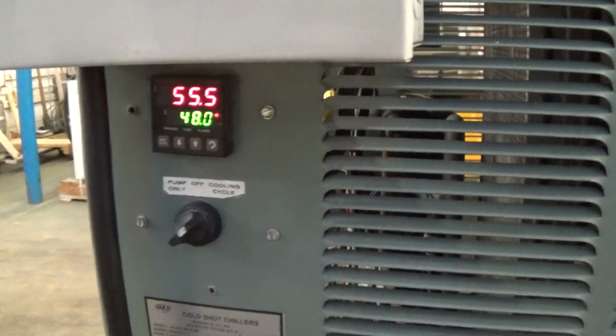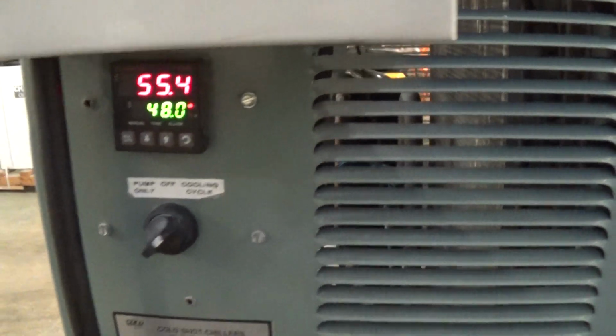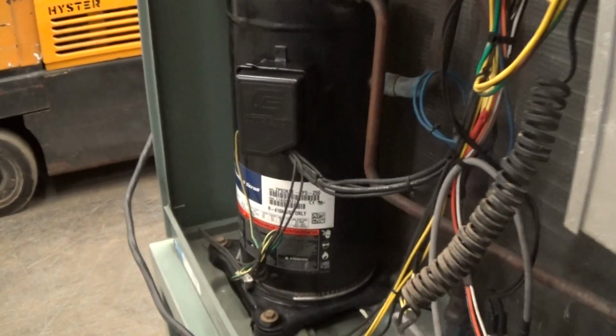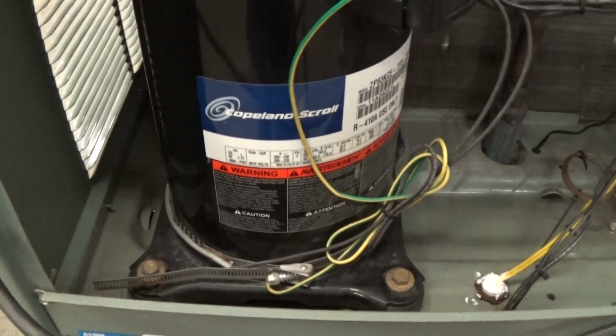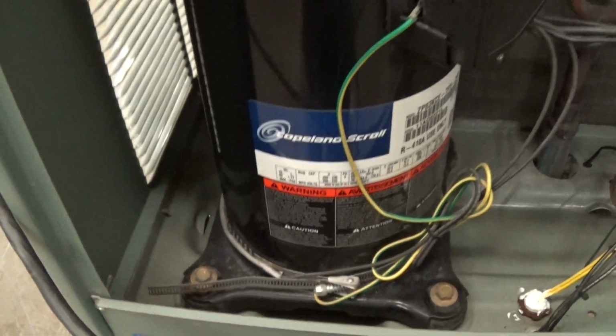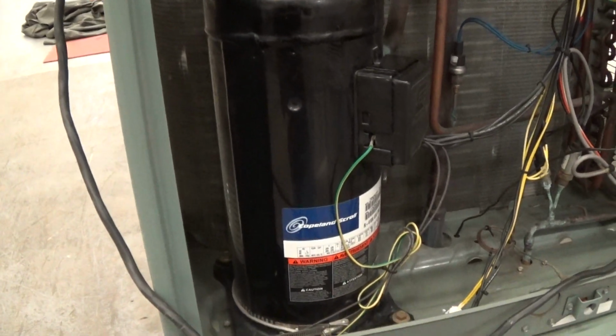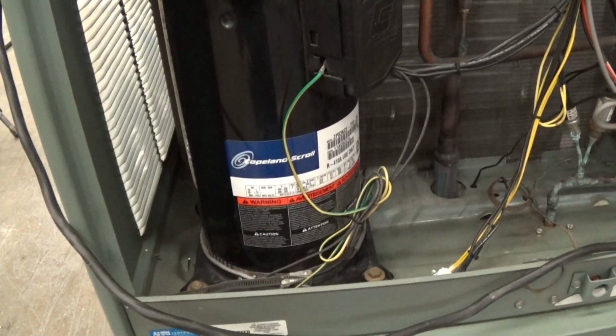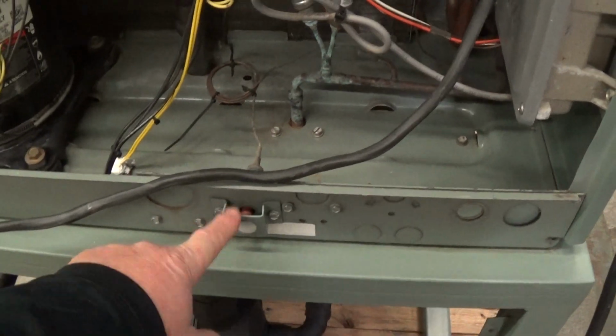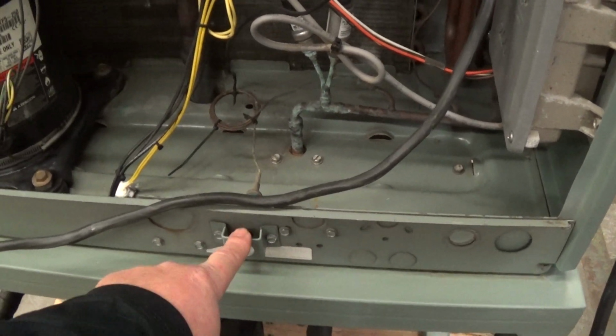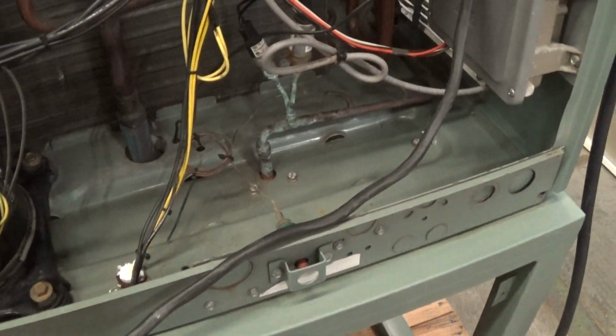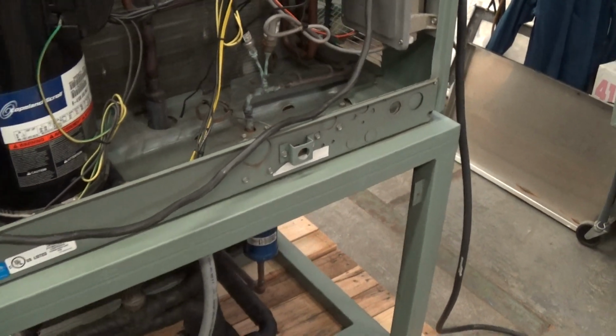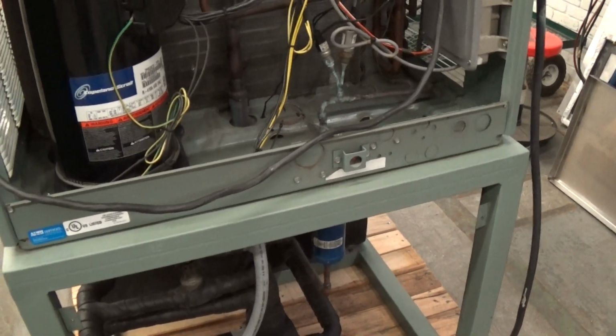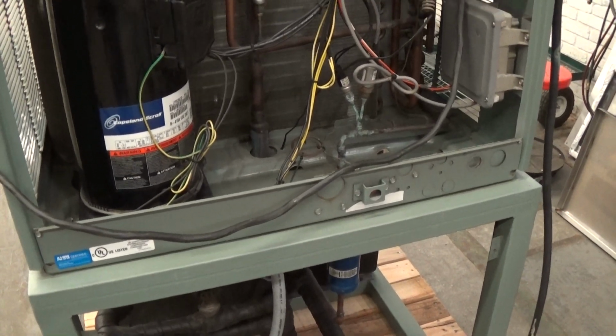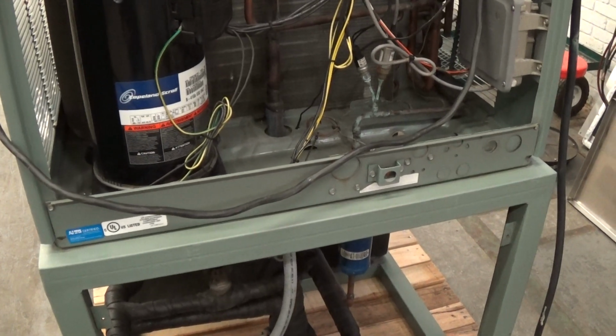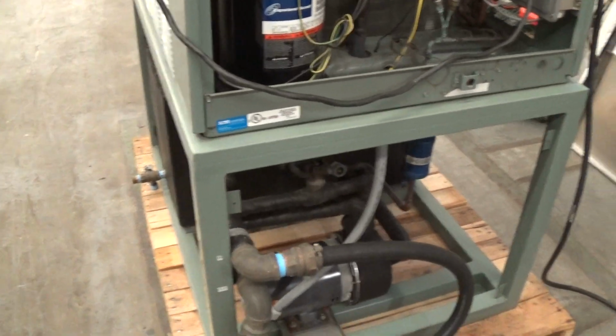So again, if you use the remote start stop, you can just leave it on cooling cycle all the time and just turn it off at the remote start stop, and then your heater band here on the compressor will always be on. And that's important to keep the refrigerant down there warm when the compressor is not running. If there's a high pressure issue, you have this resettable high pressure switch. Doesn't happen too often. That would happen in a case where either the fan stopped working on a hot day due to a fan motor failure, or if the condenser coils were so clogged, not creating enough airflow of the condenser, that it would create high refrigerant pressure for the R410A.